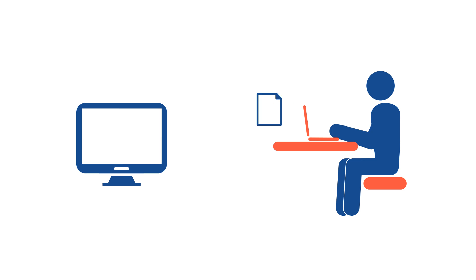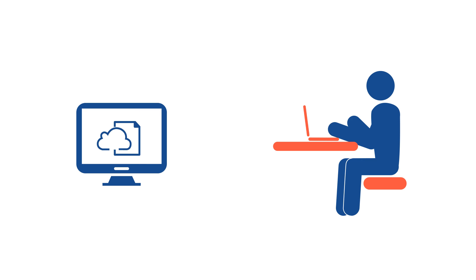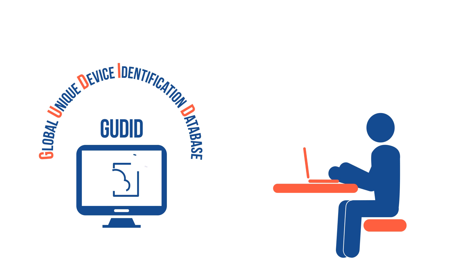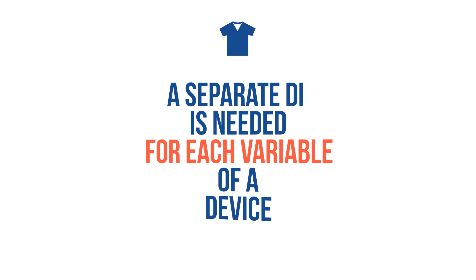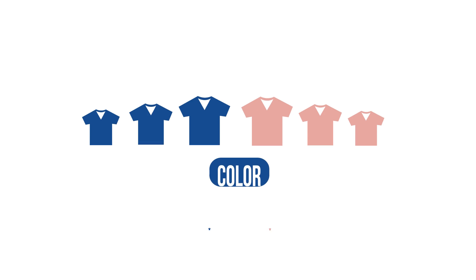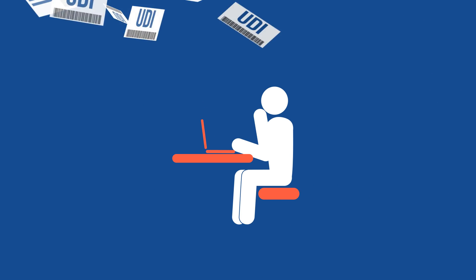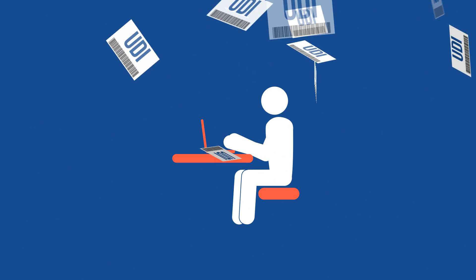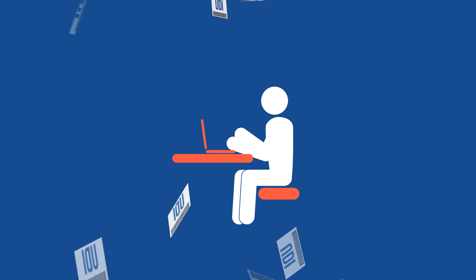Labelers must also submit information about each device labeled with a UDI to a publicly searchable database called the Global Unique Device Identification Database. A separate DI is needed for each variable of a device, such as size, color, or style, so the number of UDIs for a single type of device can add up quickly.